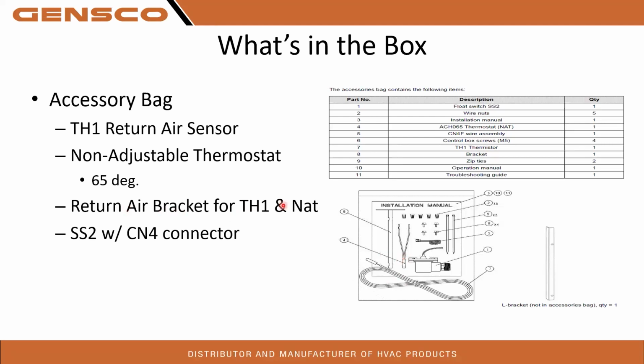It also comes with the bracket to mount those things into the return. It also comes with a condensate float safety, which is right here, along with a connector to plug this into the board. One thing to note is this condensate safety does not tie into your low voltage. Does not break your red and white. It is designed to wire into the control board on the CN4F connector. And we'll get into that a little bit more later on. But if you guys wire that into your 24 volt, you're going to get a thermostat error.